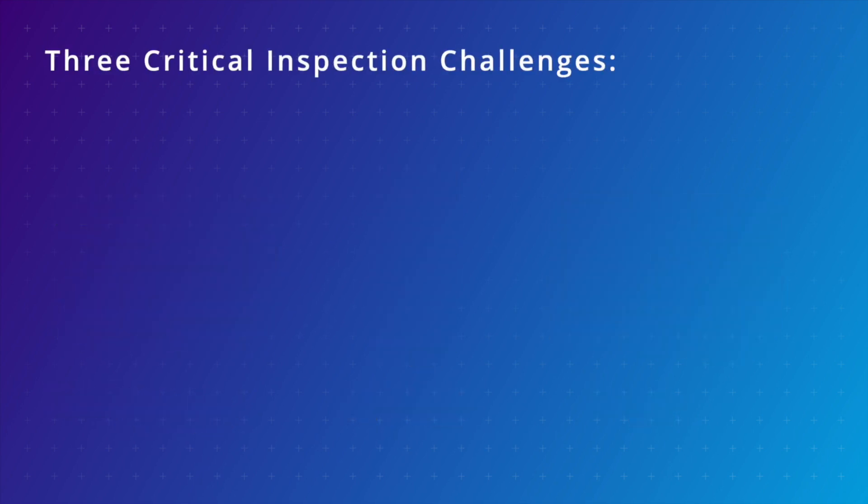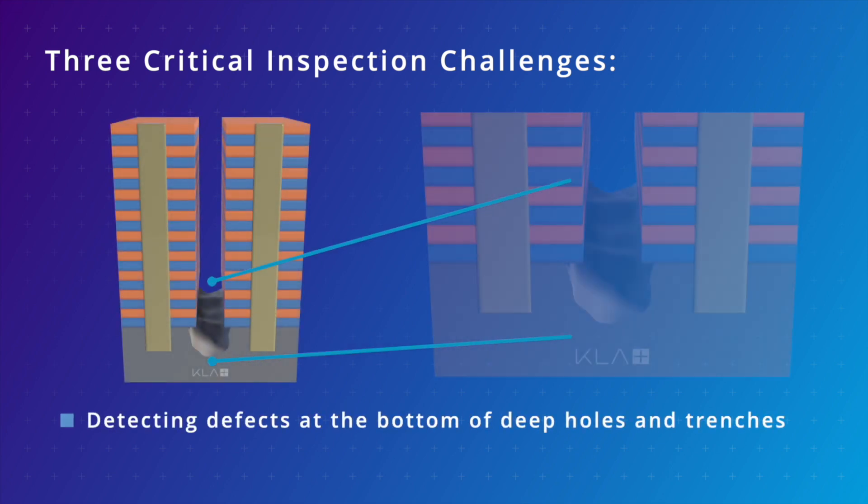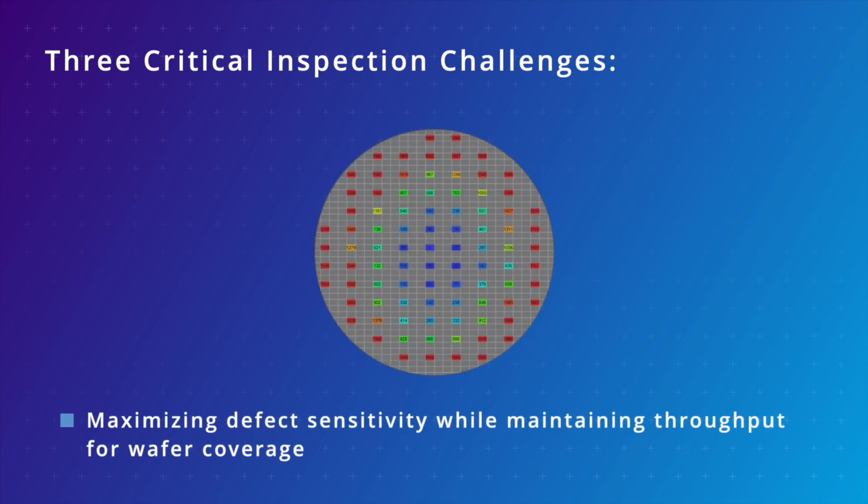There are three critical inspection challenges that must be addressed. Detecting defects at the bottom of deep holes and trenches. Finding sub-5 nanometer patterning defects. And maximizing sensitivity while maintaining throughput for wafer coverage.